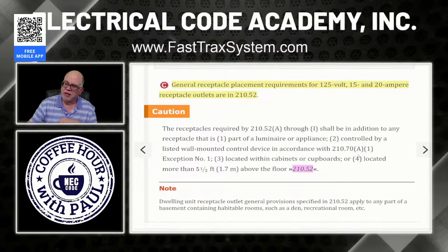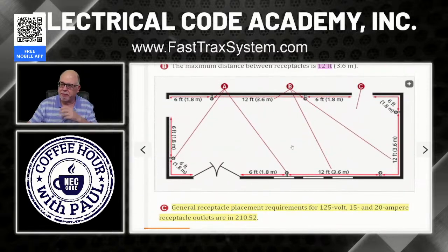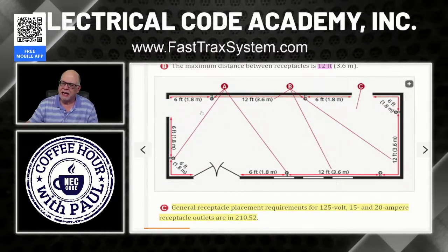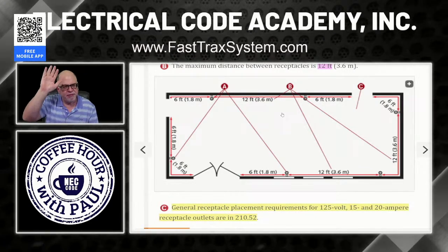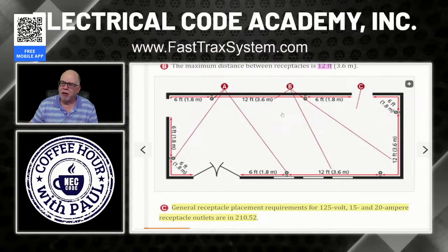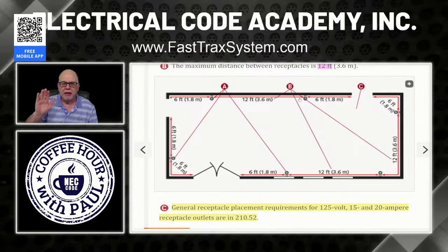And then lastly, located more than 5.5 feet above the floor. So let me give you an example here. Say this is my bedroom, and I'm laying out my receptacles, a 6 foot, 12 foot rule, but I want a receptacle up high for a flat screen TV. Now, if that receptacle is, let's say it's this one right here, okay? So let's say it meets the spacing, and you put it up 4 feet, that's perfectly fine.